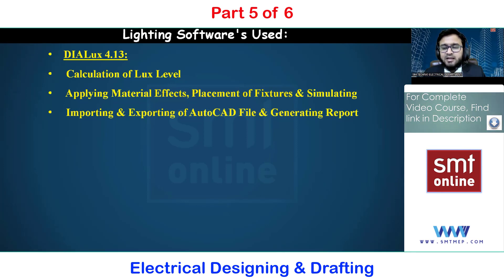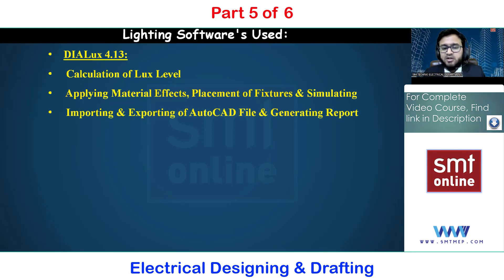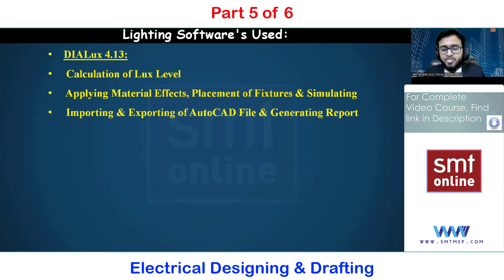In the lighting calculations there is a parameter called CUF — the Coefficient of Utilization Factor. This factor tells us how much light is going to be absorbed and how much is going to be reflected, so based on that we can exactly find out the number of lighting fixtures required.